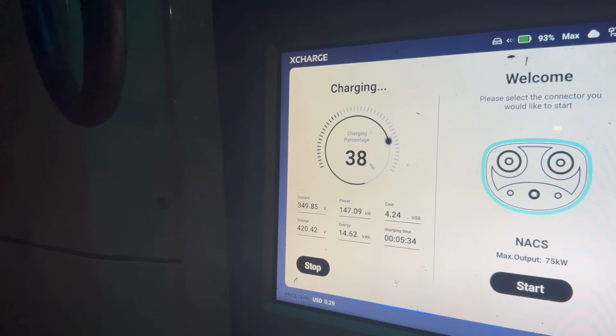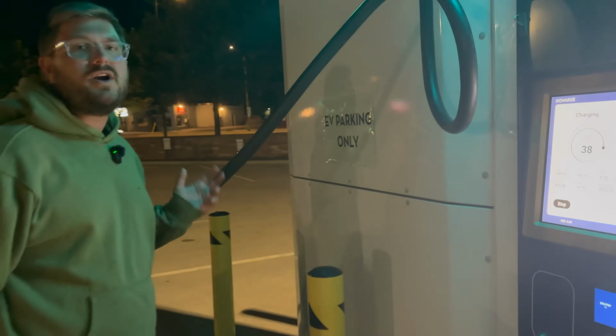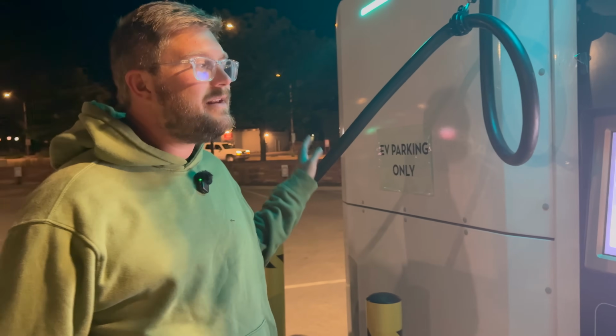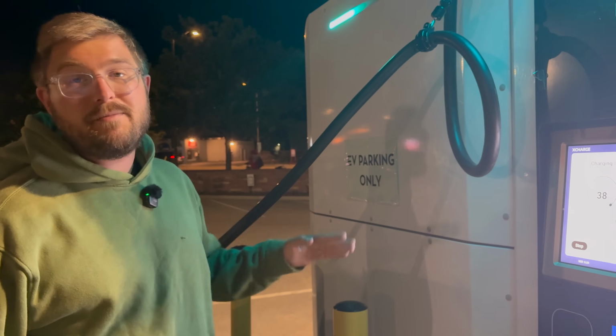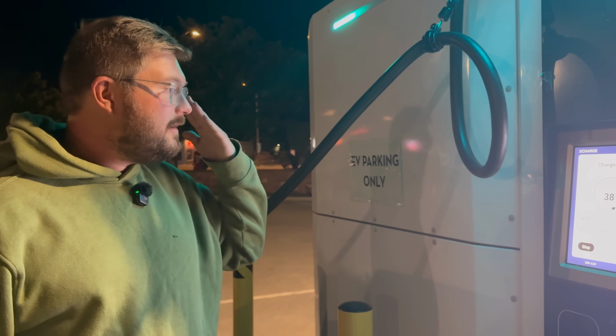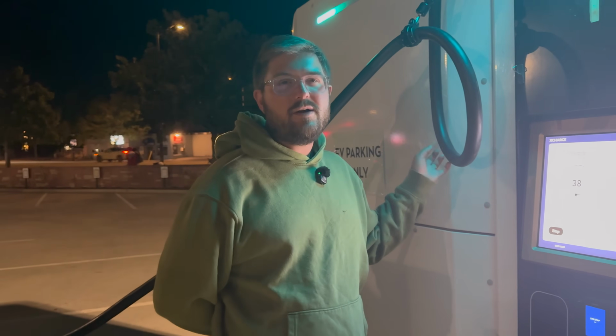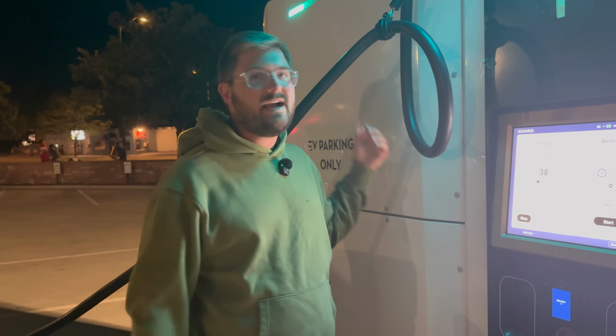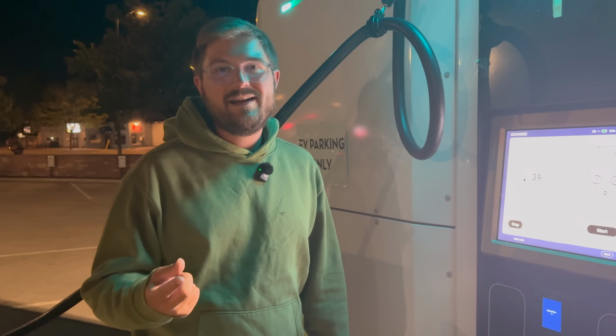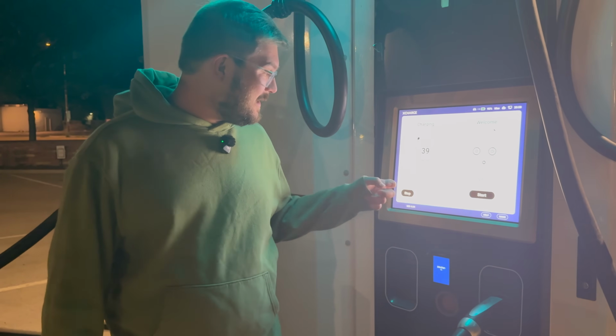The nominal rating of the cable is a very conservative number, so many charging manufacturers and cable manufacturers are okay with a boost profile. However, it shouldn't be based on an arbitrary time limit—if the cable's roasting hot, it shouldn't do it. The best way to test if it's temperature based is to unplug it and plug it back in, and see if we get another 5 minutes of boost. So guess what we're going to do?